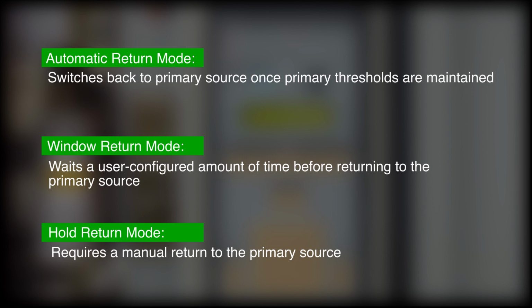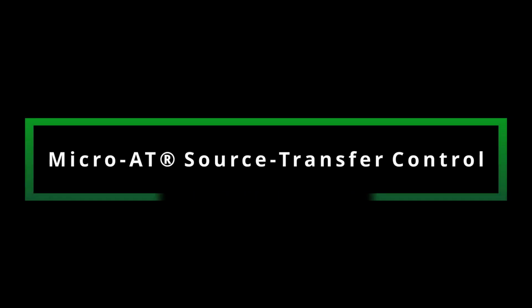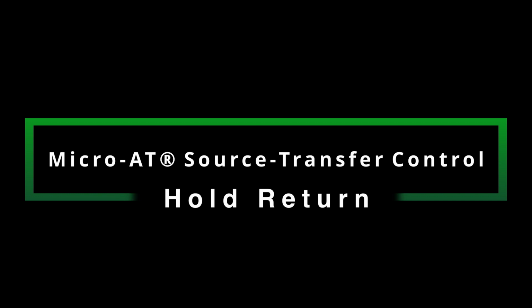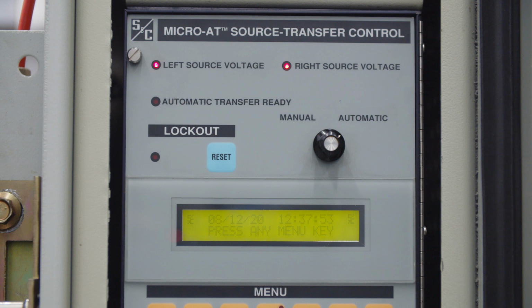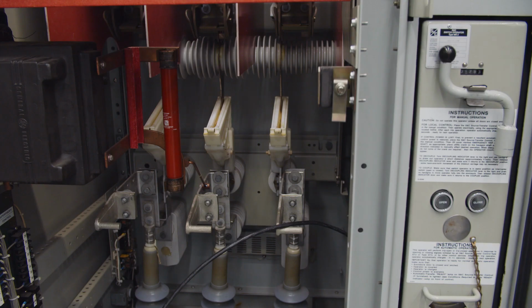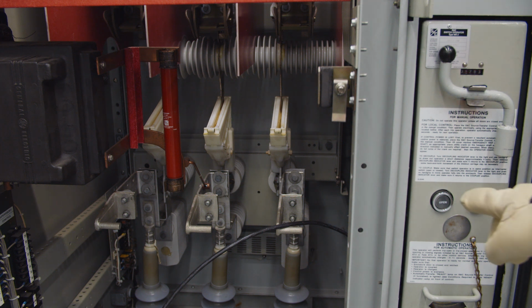Here are steps to take to return the control to the automatic transfer ready state if hold return mode is active. After the control is operated, it will be in automatic mode, but the red LED lamp Automatic Transfer Ready mode will not be lit. The switches connected to the control will not be able to operate until the control is put into manual mode.